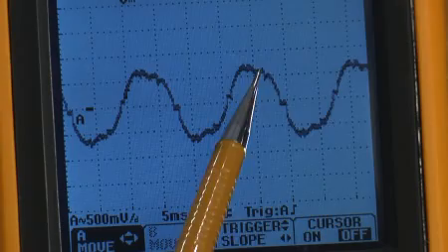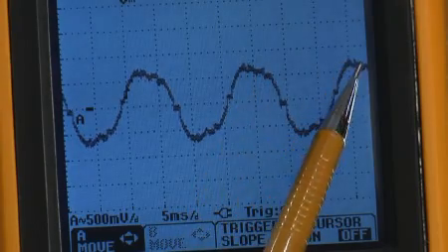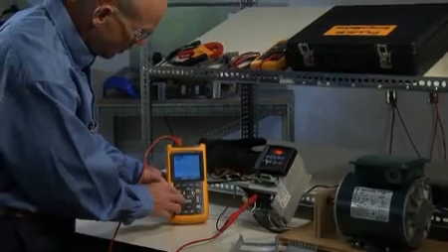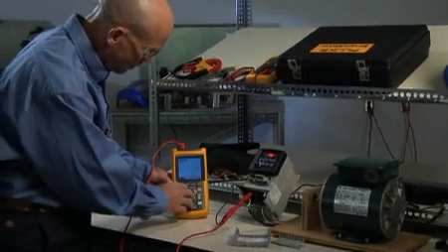Flat-top waveforms are typically caused by non-linear loads attached to the same feeder circuit. Thanks to the scope meter, we now know that the problem doesn't lie with the VSD or the motor.